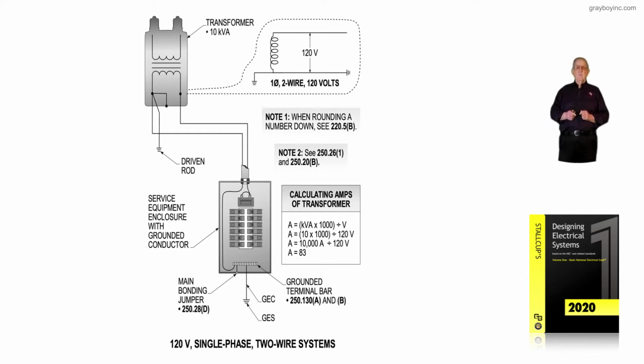So basically we could, in the 2020 NEC, go to our Table 310.16, and based upon a 75-degree terminal, a number 4 conductor could be used to supply that breaker. And that breaker could be 90 amps or 80 amps, depending on if you round down or round up, whatever would meet your need.